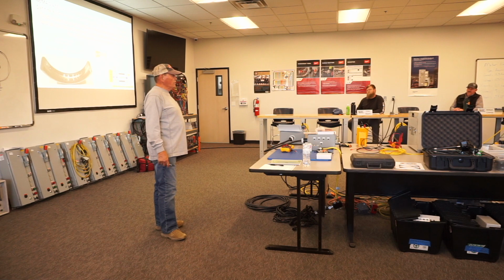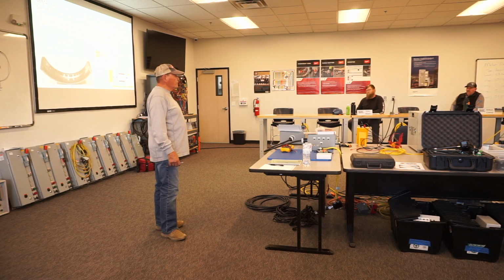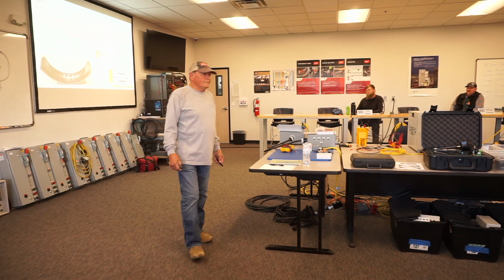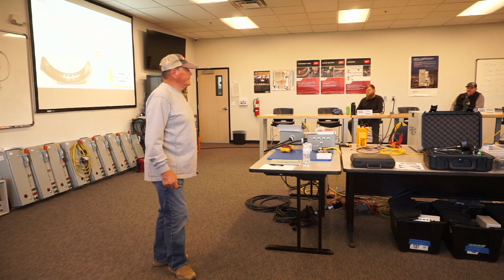Because in the real world, the neutral is going to carry hardly any current. The neutral pulled by the power company into your service is going to be half the size of the phase conductors. They know there's going to be no current on that neutral conductor. Why don't we? How come we don't? Our fix is to pull separate neutrals. Well, that raises the price of the project. Well, why don't we just get rid of the problem? We go back to pulling round robins? I don't know.